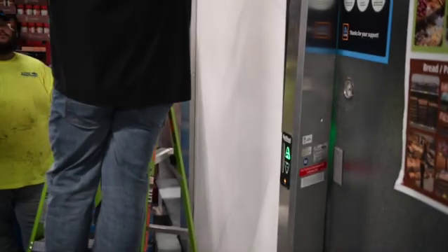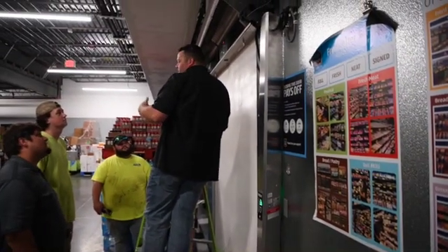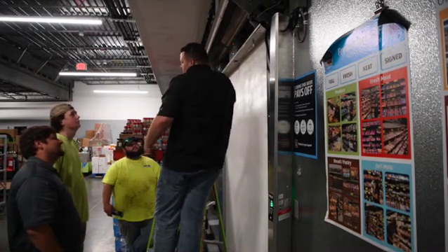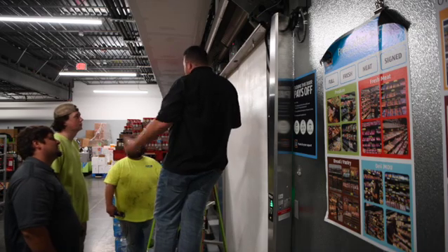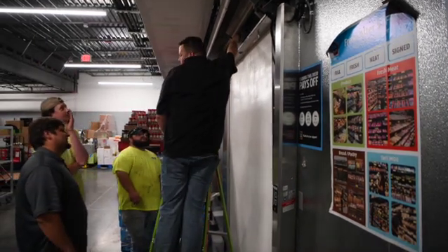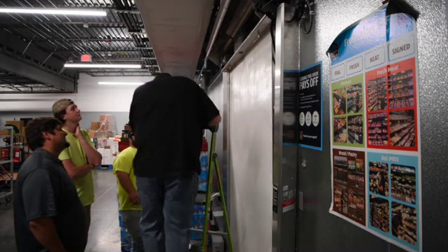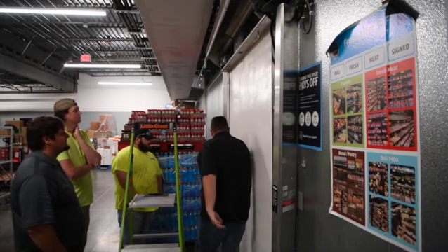But before I turn this power off, jog mode. If you ever call me or Shane, we say, let's put it in jog. You hold the 2 buttons down, these two. So if the door moves in jog, everything mechanically is fine. Usually I get people on the phone and they're holding these and I'm like, it ain't doing it. And I was like, well, no, of course not. But you'll shut your power off and come in here.